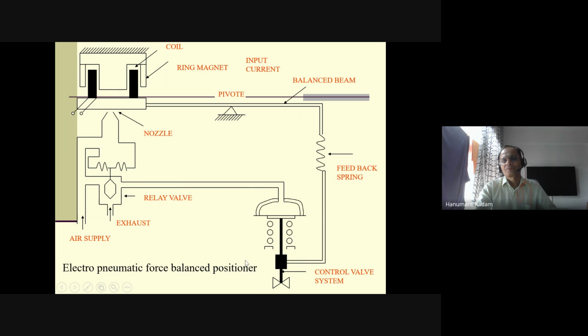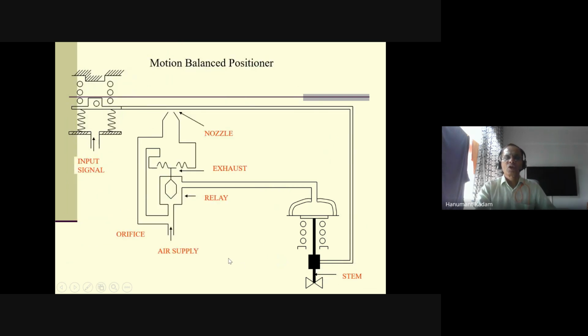This is a valve. In the motion balance type of positioner, you can see here the electro-pneumatic: input signal, again the same thing. Pivot, this is the flapper, and this is a nozzle. So this is a flapper nozzle system: air supply, relay, and this is the stem. Just a minute.